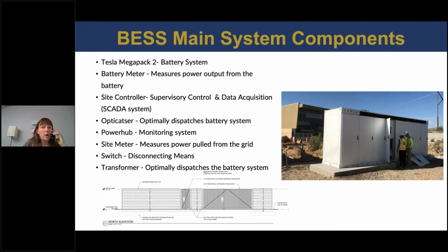I'll note that our battery system at this site does not intertie with the solar system. The two are separate systems: the BESS is connected with a radial loop, a 15 kV radial loop around the school itself, and the solar runs into and interconnects with individual buildings, which I'll go over later. The solar does not charge the battery on the system, which a lot of people find confusing, so I want to make that crystal clear.